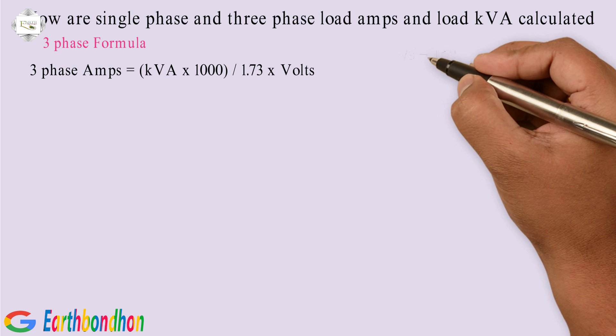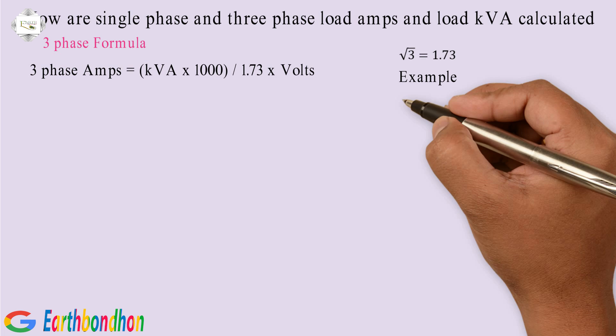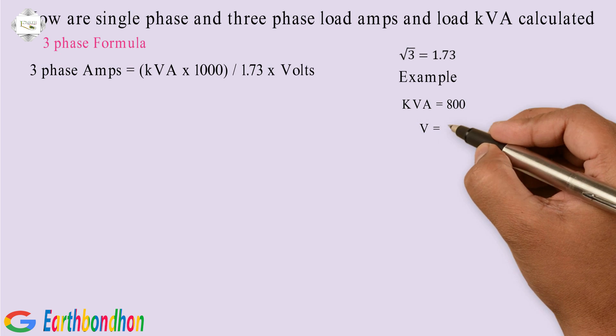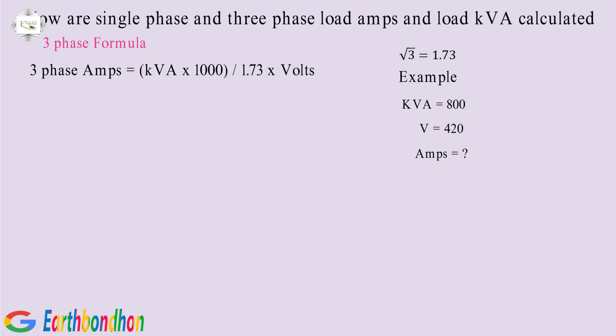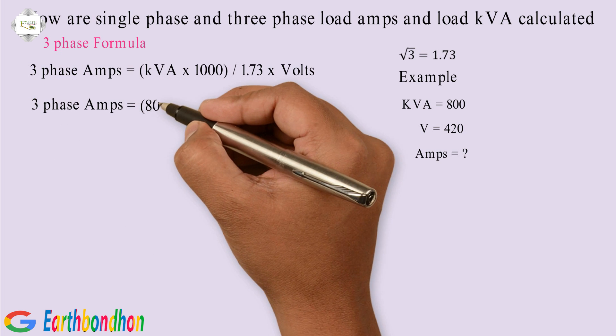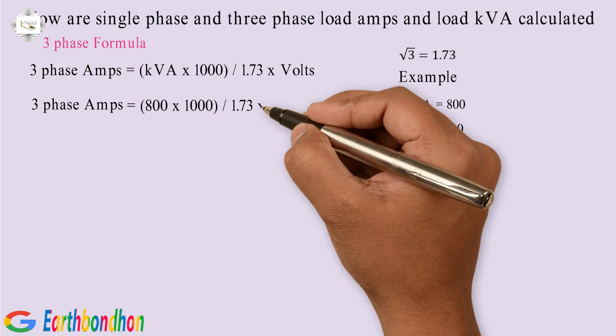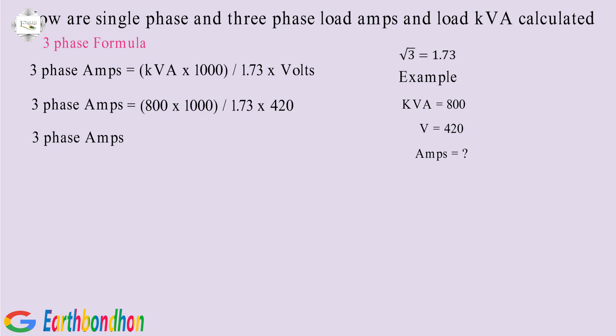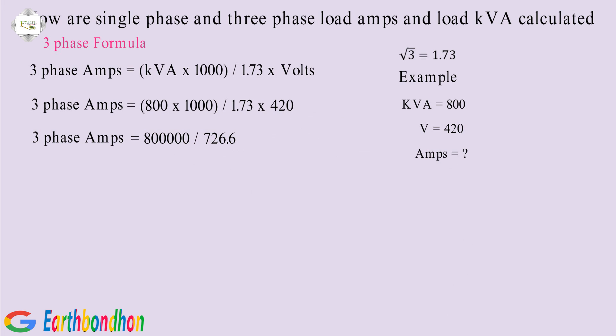SQRT3 equals 1.73. Example: KVA equals 800, V equals 420, SQRT3 equals 1.73, amps equals unknown. Amps equals 800 multiplied by 1000, divided by 1.73 multiplied by 420. Equals 800,000 divided by 726.6.